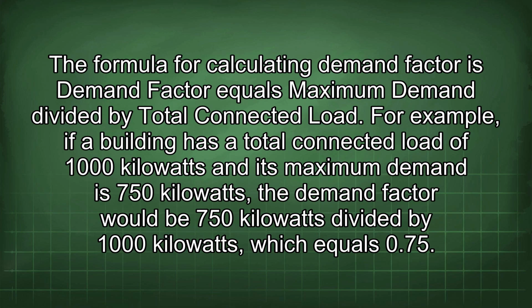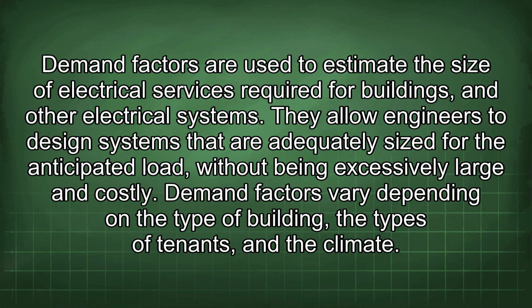For example, if a building has a total connected load of 1000 kilowatts and its maximum demand is 750 kilowatts, the demand factor would be 750 kilowatts divided by 1000 kilowatts, which equals 0.75. Demand factors are used to estimate the size of electrical services required for buildings and other electrical systems. They allow engineers to design systems that are adequately sized for the anticipated load without being excessively large and costly.